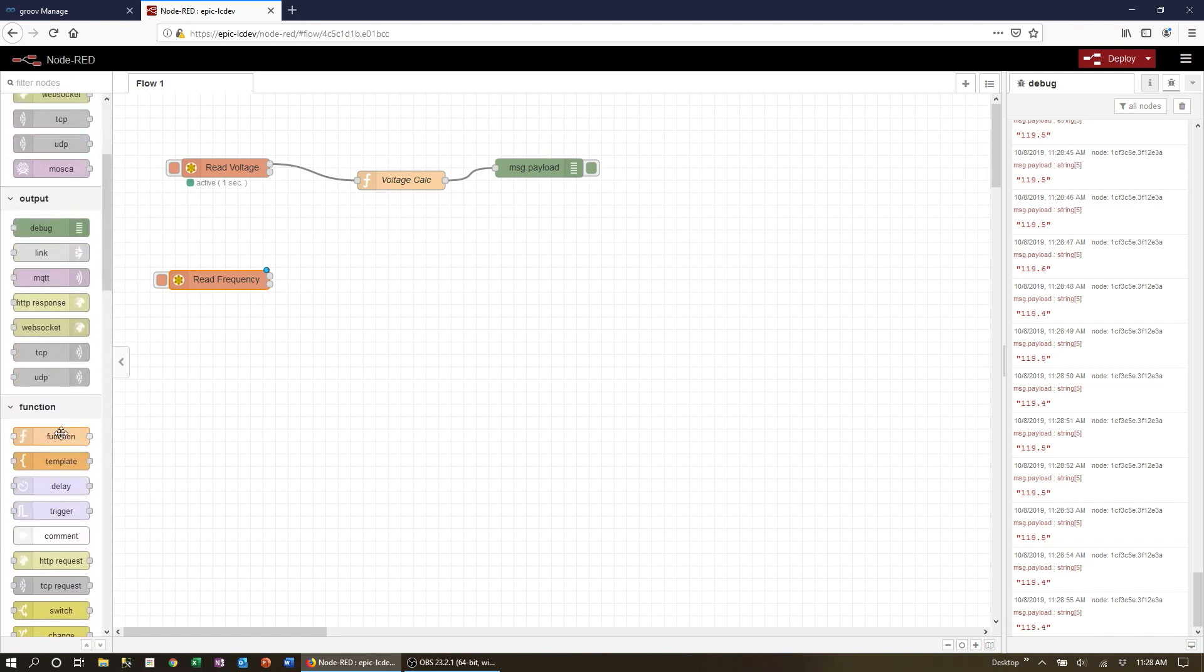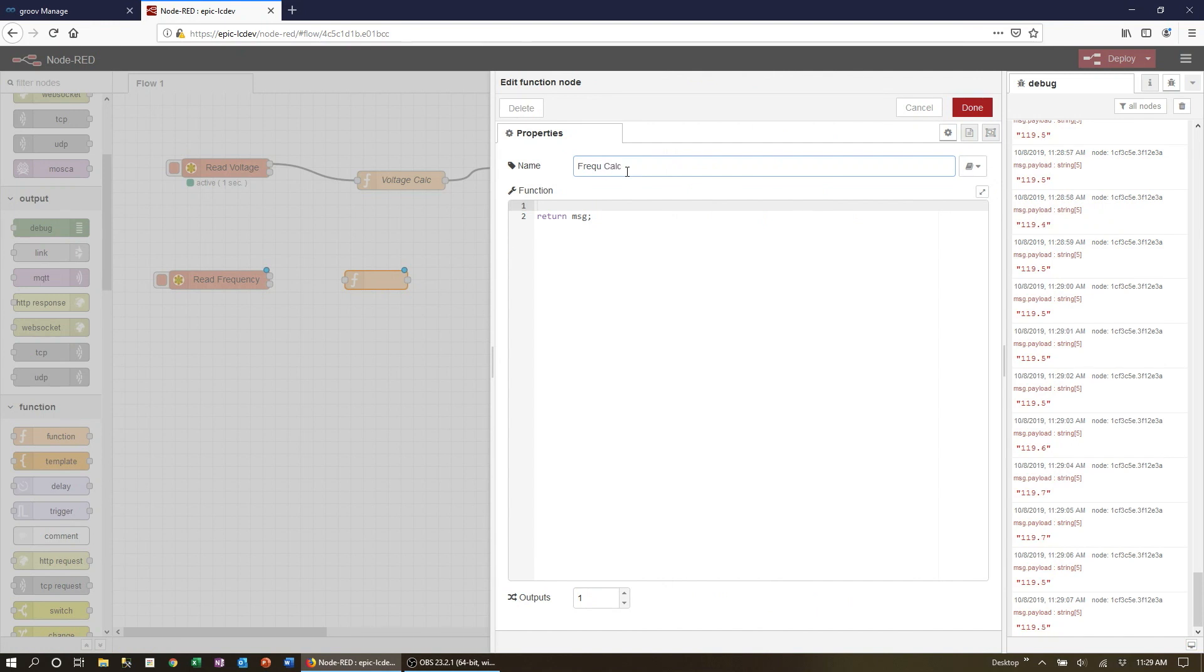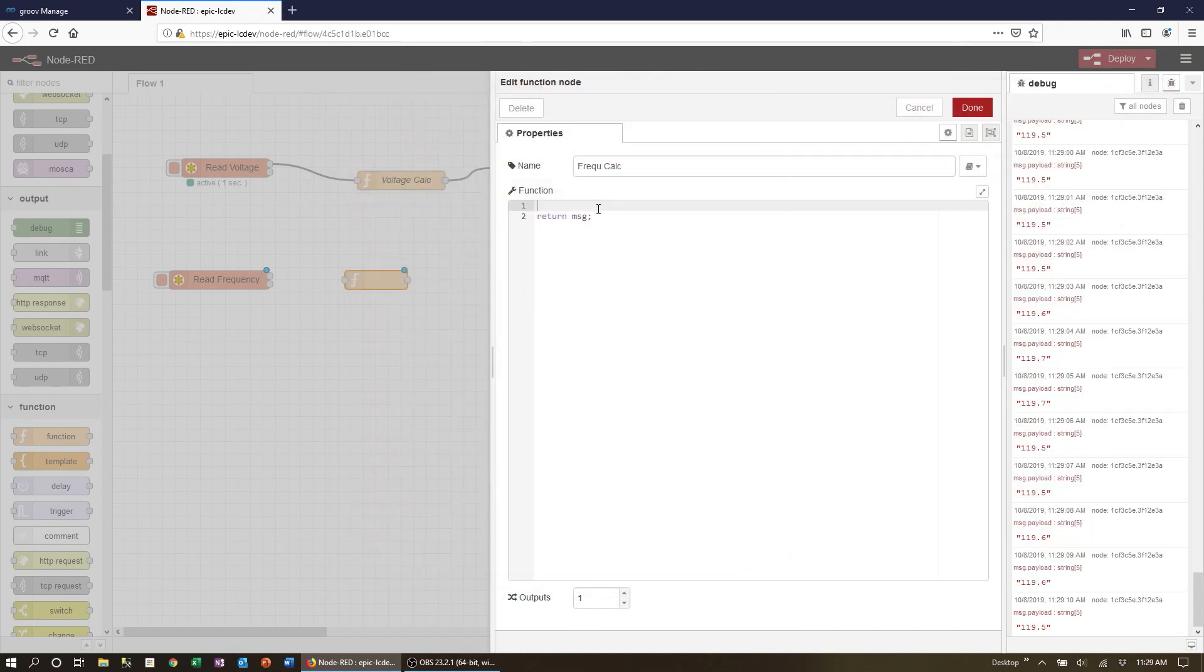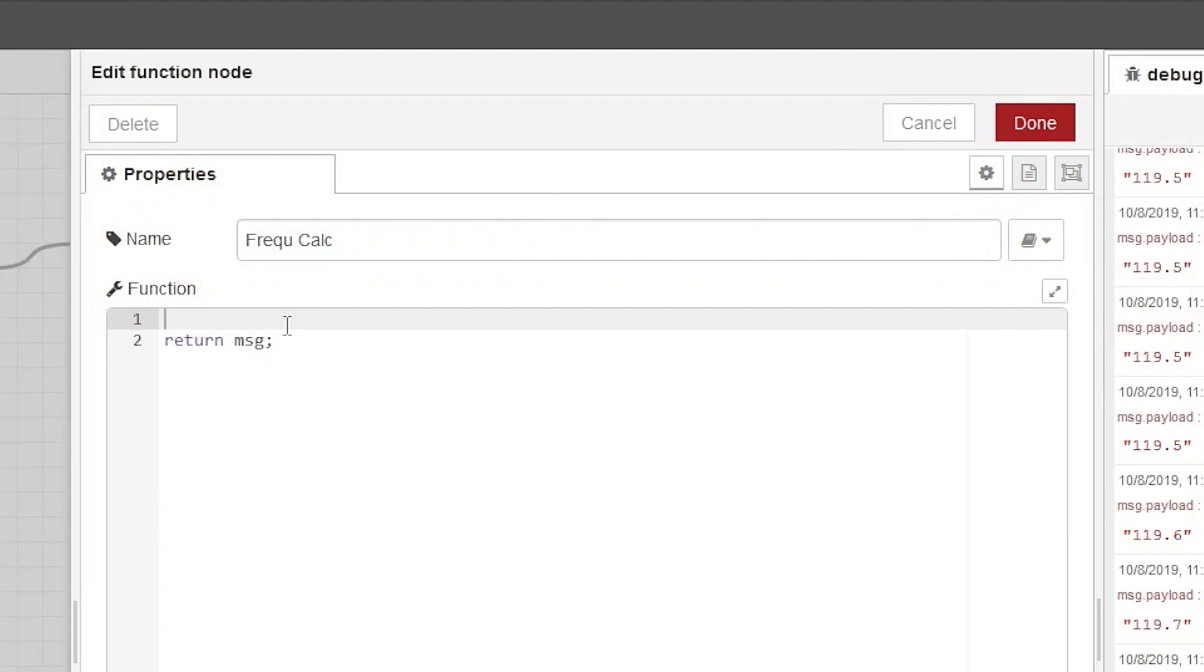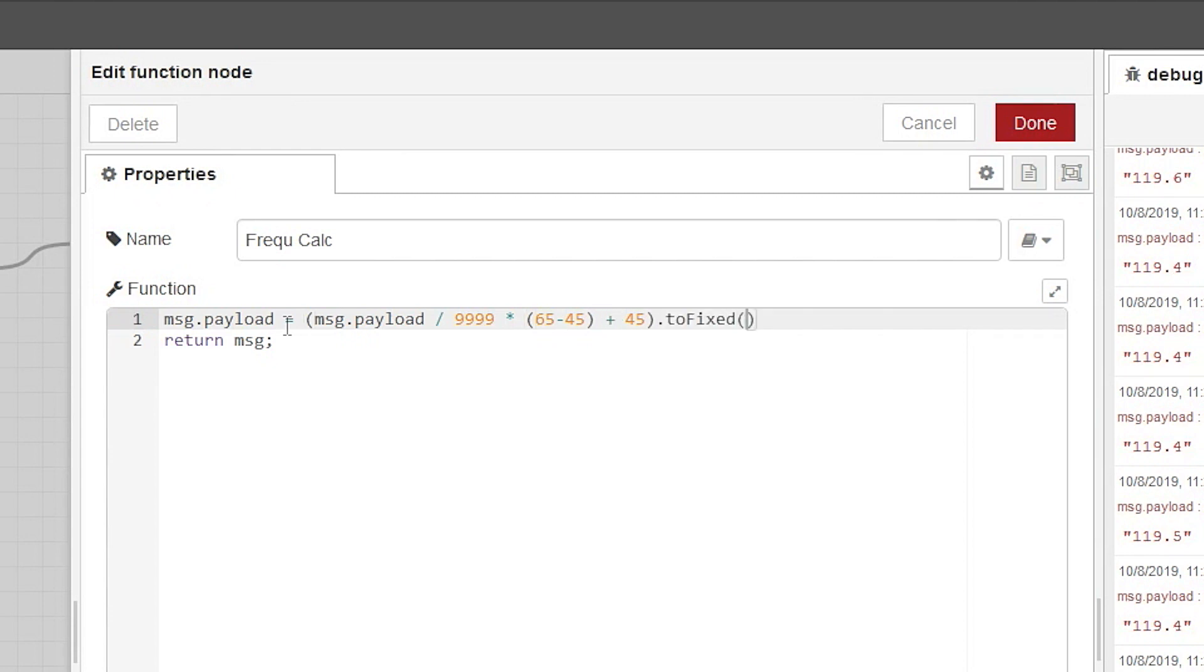Drag a function node over, give it a name, frequency calc. Now let's look in the manual to see what the upper and lower limits are for the frequency. Enter the formula: message dot payload equals message payload divided by 9999 times 65 minus 45 plus 45 to fixed 2.